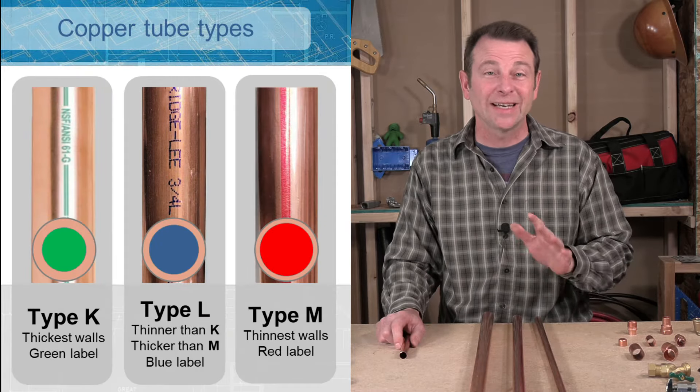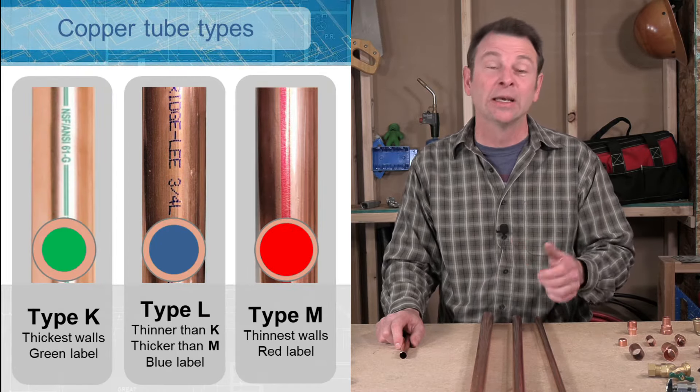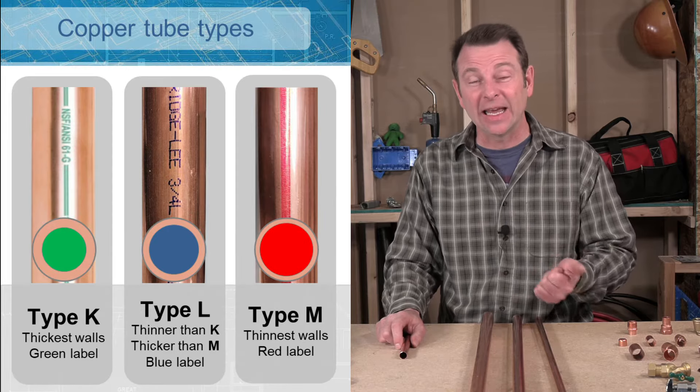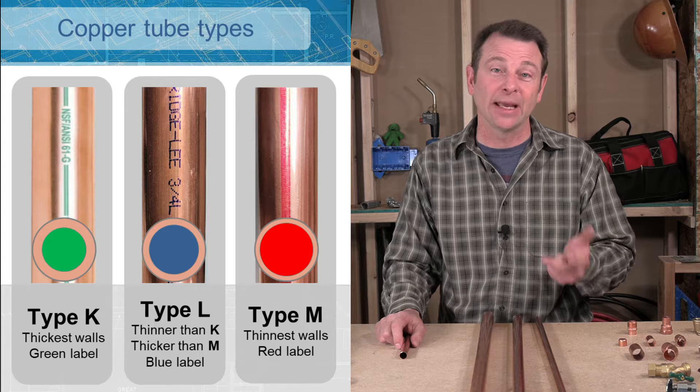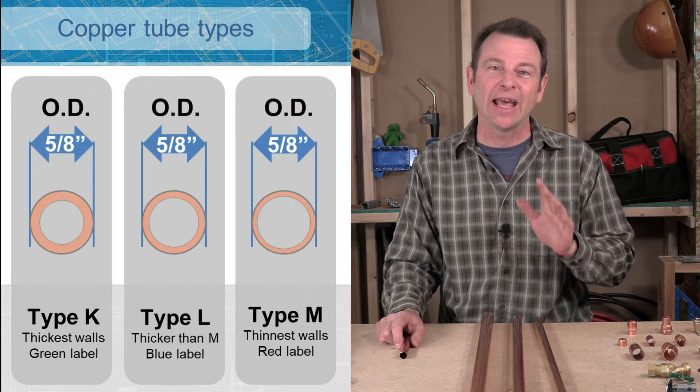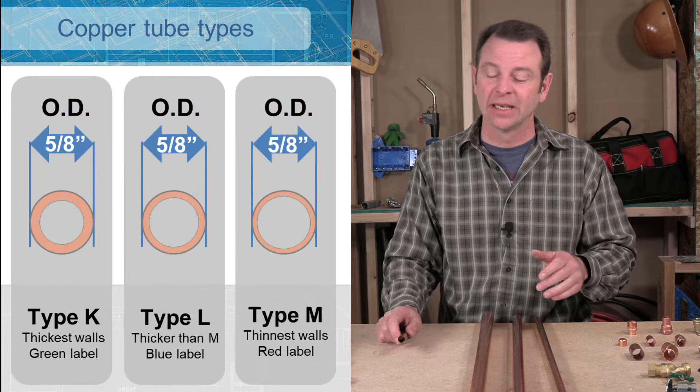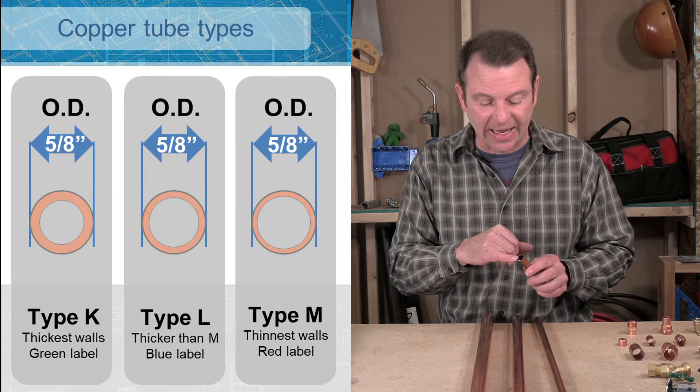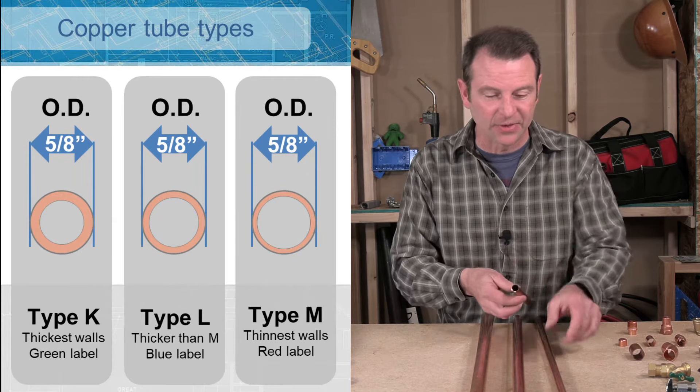There are three types of copper pipe that you'll see as well. They're called out by a letter of the alphabet. You might see type K, type L, or type M. Type K will have the heaviest wall of all the pipes. And what I mean by the wall of the pipe is the thickness of the outside of this pipe.